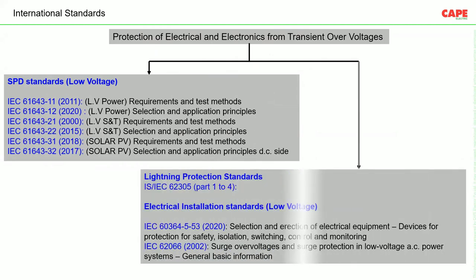These are the various standards for SPDs, like IEC 61643 part 11, 2011, which explains the various requirements and test methods of an SPD. 61643 part 12 tells about the selection and application principle of an SPD, how to select an SPD for what application. 61643 part 21 discusses the same requirements and test methods for signal and telecom SPDs, whereas 61643 part 22 discusses selection and application of signal and telecom SPDs, that means data SPDs. 61643 part 31 and 32 discuss the same thing for solar PV SPDs.